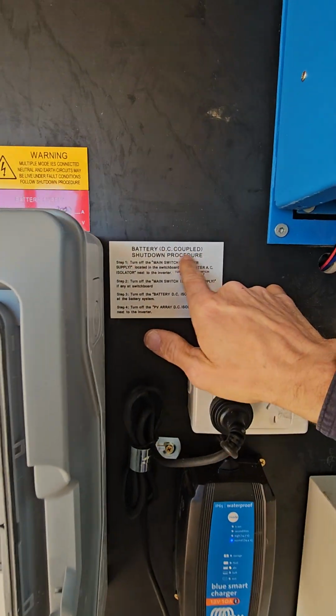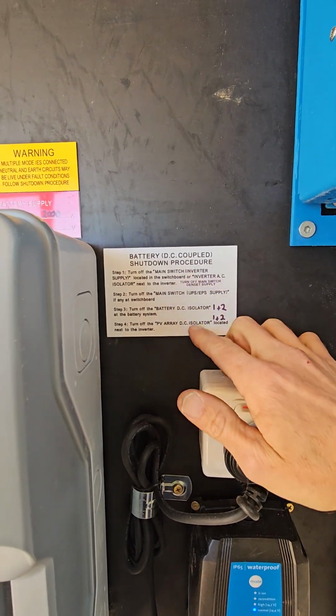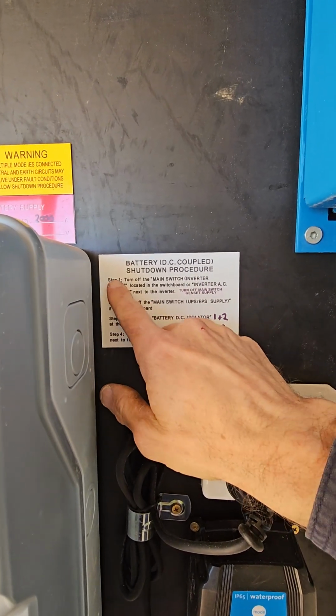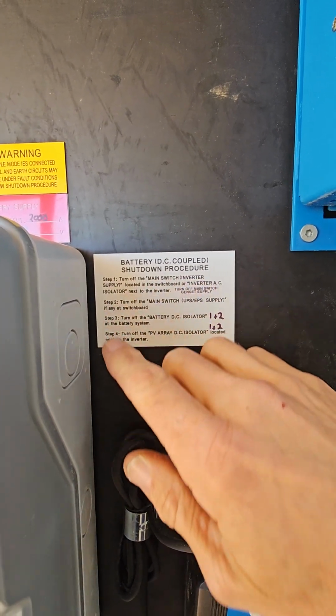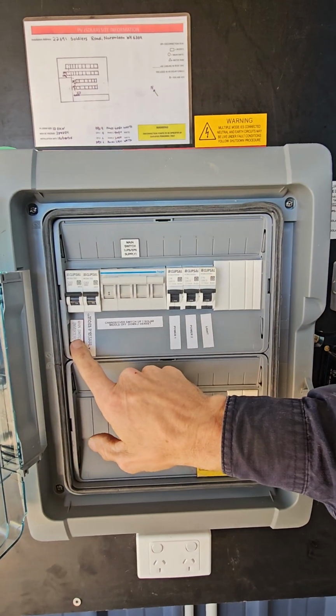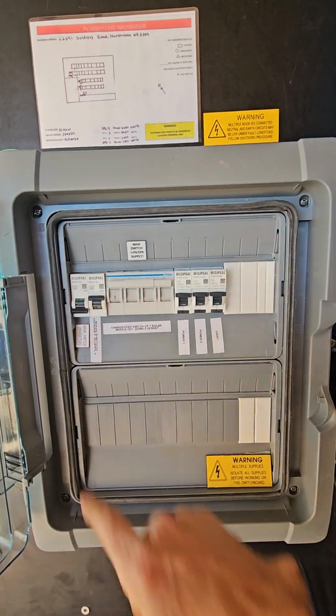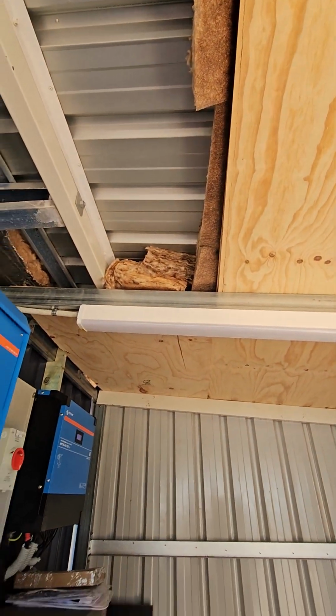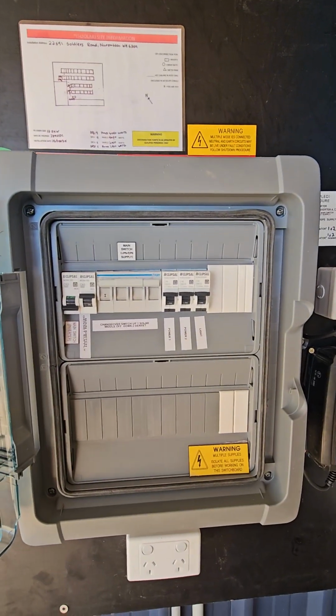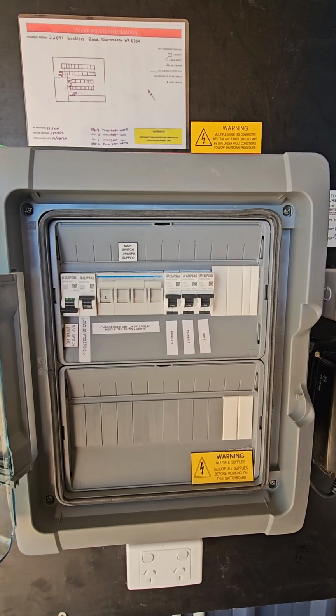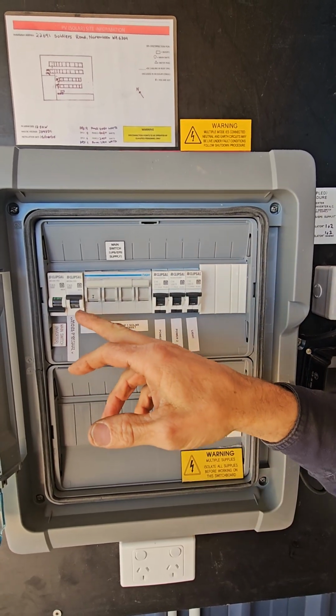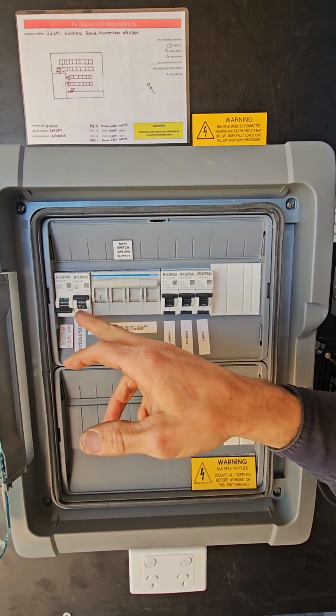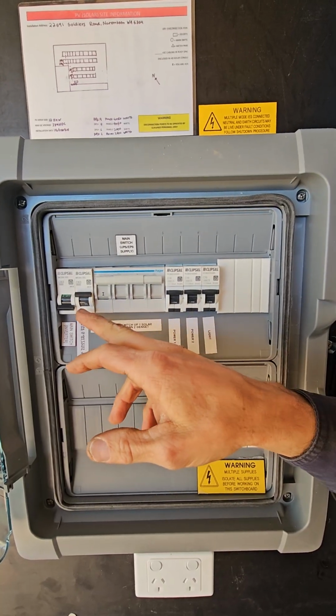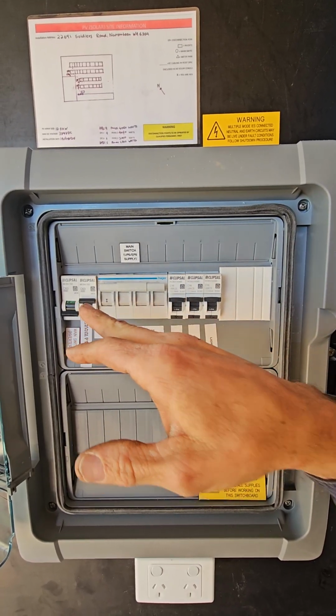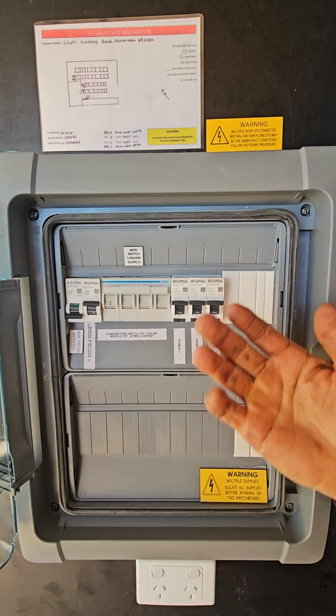So, battery DC coupled shutdown procedure, so that's the type of system you have, a DC coupled system. So step one is turn off the main switch inverter. So you've got main switch inverter here, so basically turn that off, and then you can see our lights just went off. So that's the main supply to this switchboard, the main switch inverter, so obviously that's why the power's off. Now if the generator was running, then we would have power from the generator at the moment through that system.